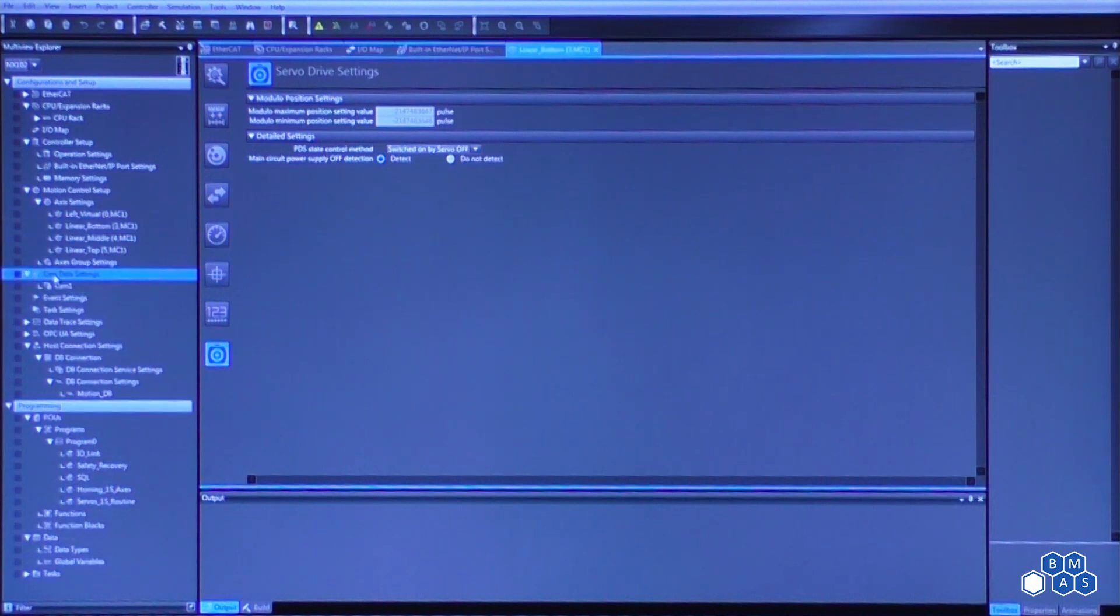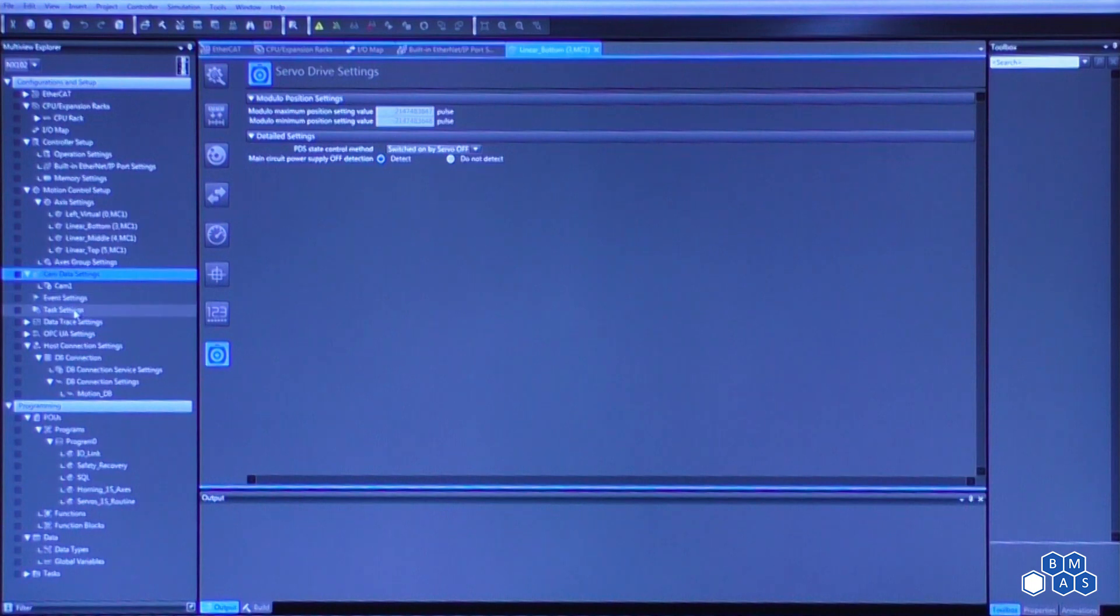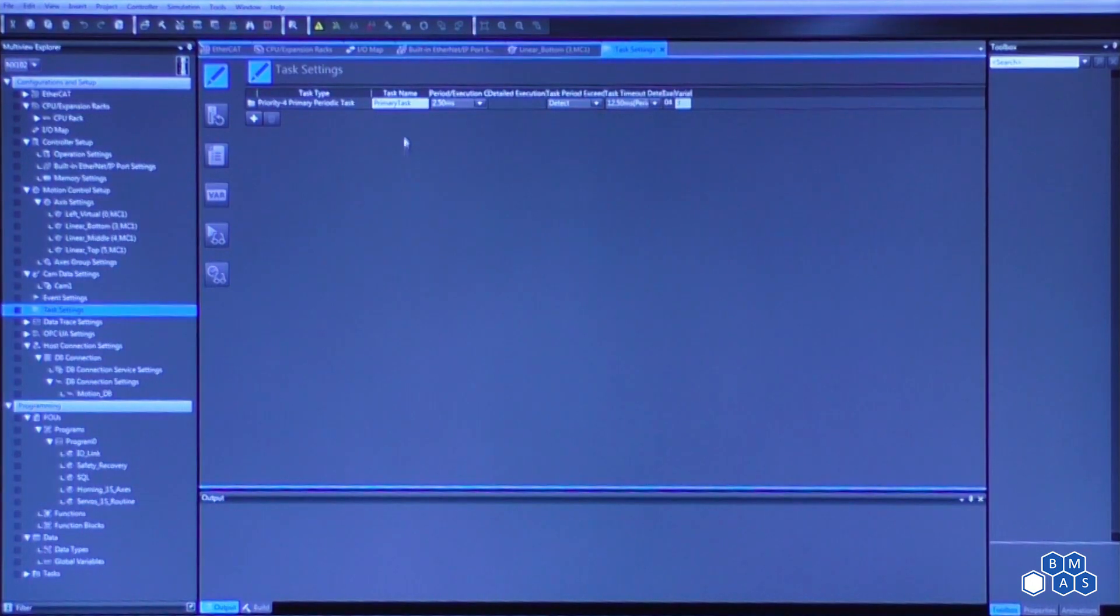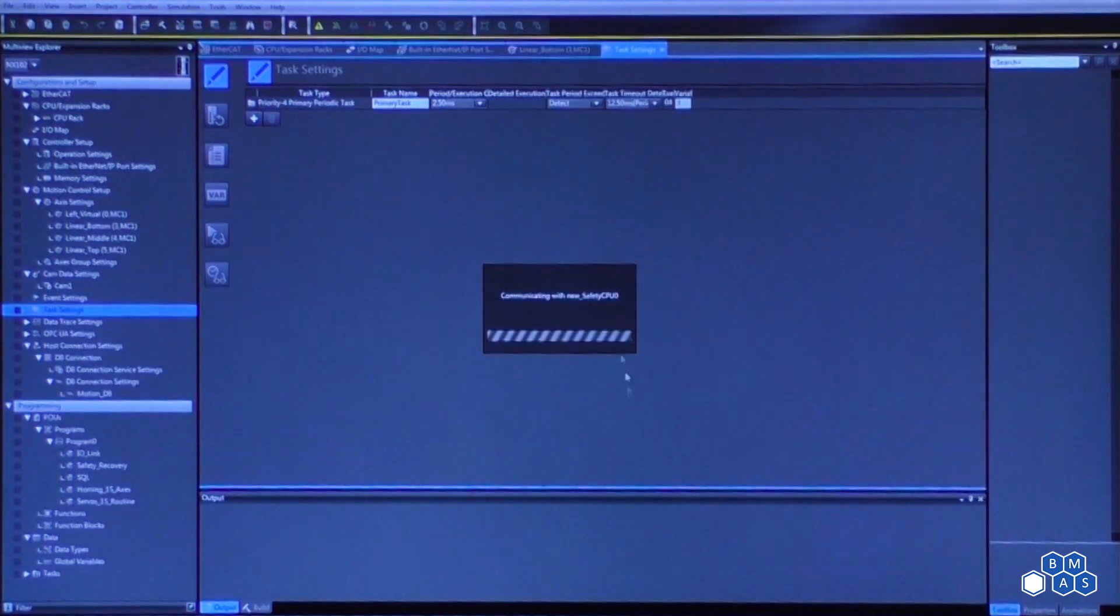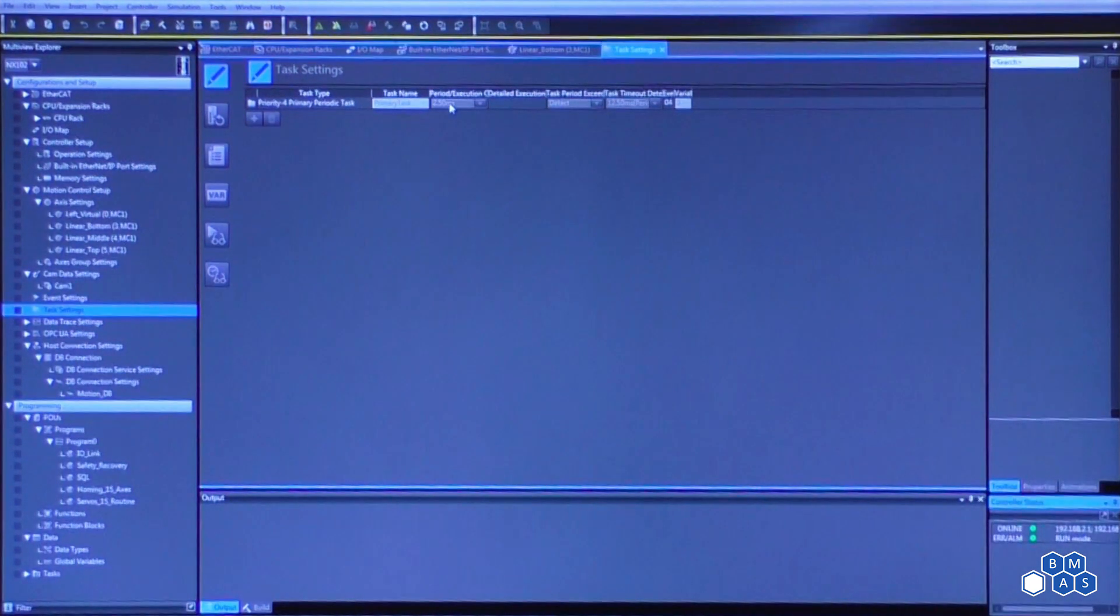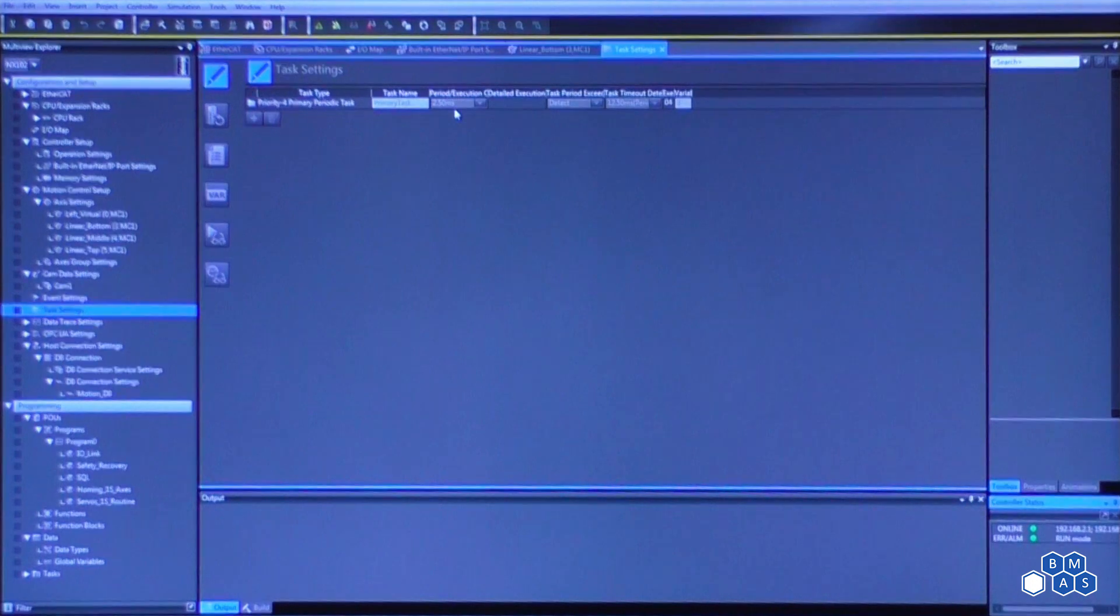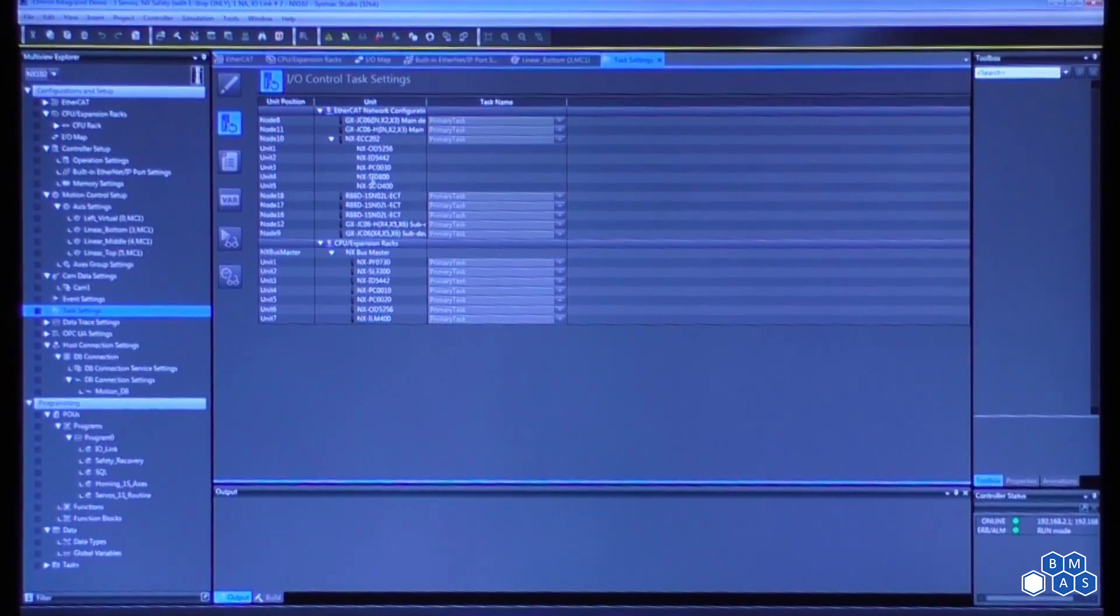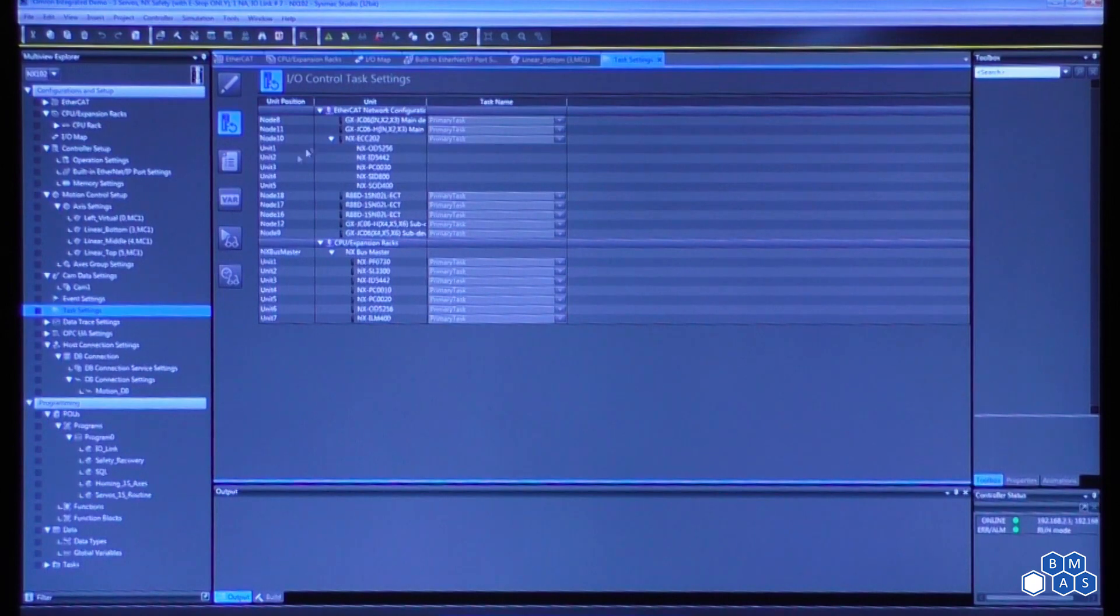Moving down, if we had any camming, we can set up some camming profiles. A nice one that I like to show is our task settings. So as we come into our task, you'll get an idea of how fast the processors are. So the setting that I created here was for a 2.5 millisecond ceiling scan time, not to exceed. And as we're working through, you're going to see that all of the IO and all of the EtherCAT devices are applied to that primary task with that 2.5 milliseconds.